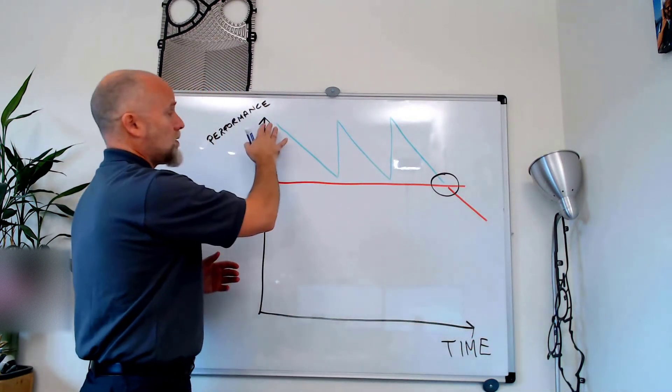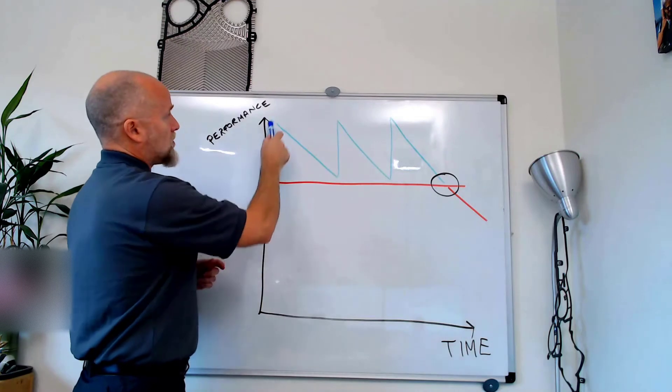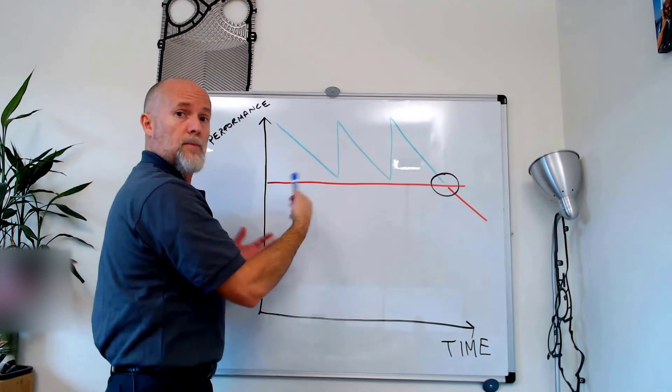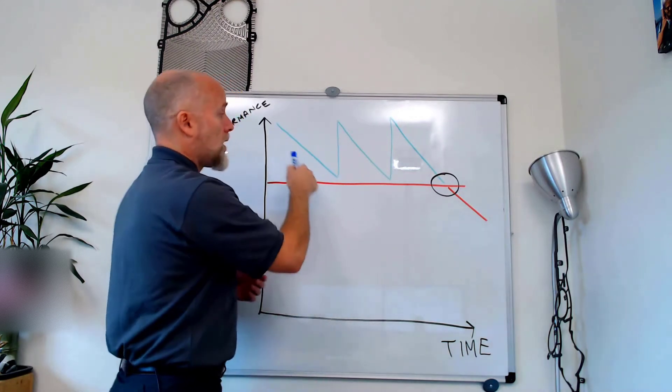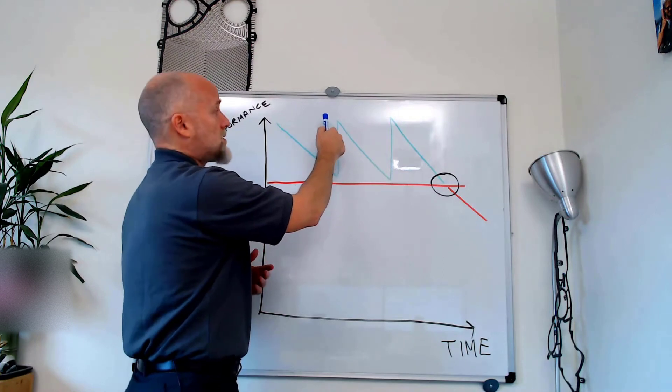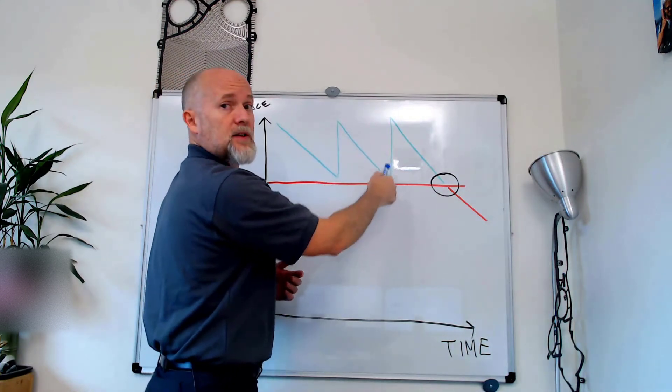So you start with a new heat exchanger and of course you have the top performances. And then as time goes by the heat exchanger fouls up and then you run a CIP and you bring it back to the original performances. Then in time it fouls up again.